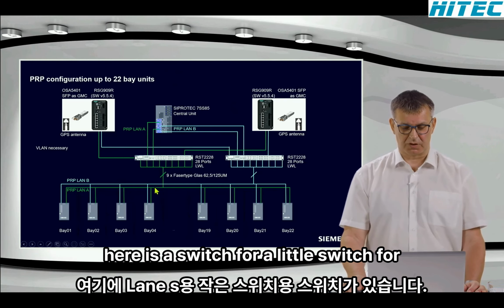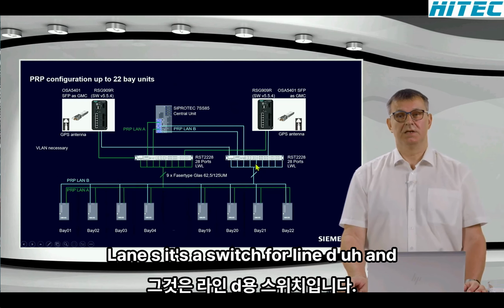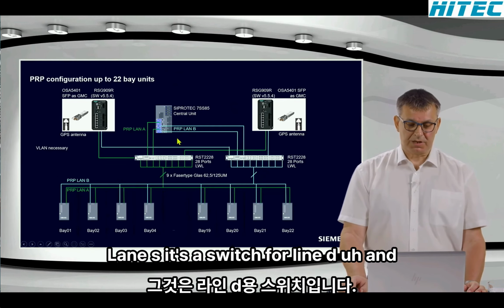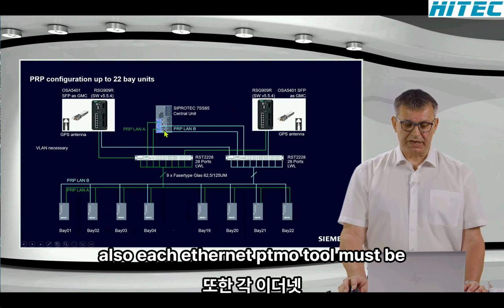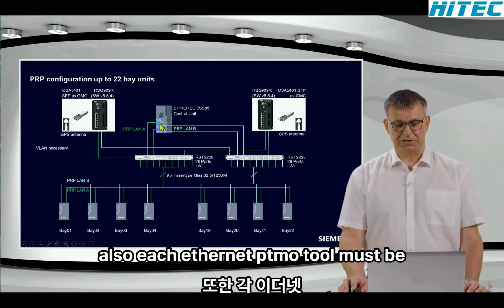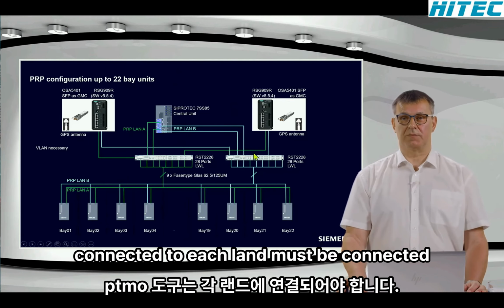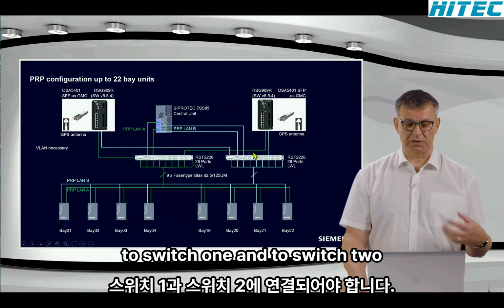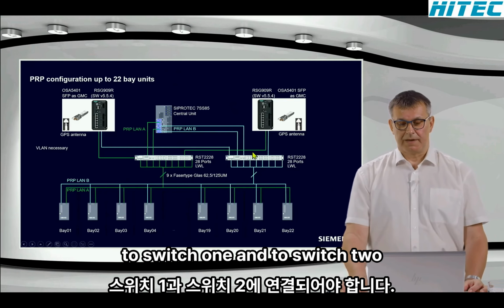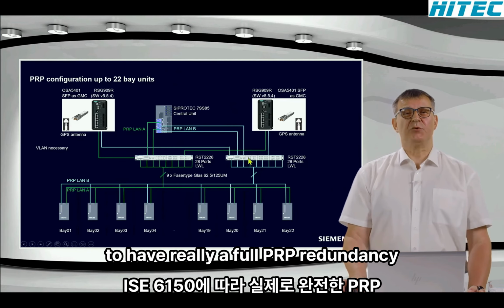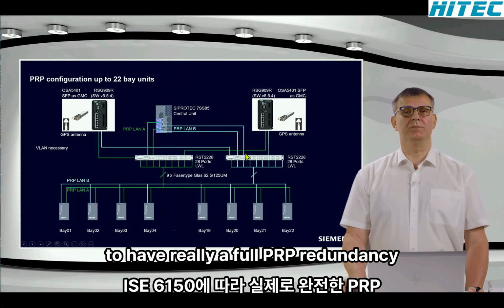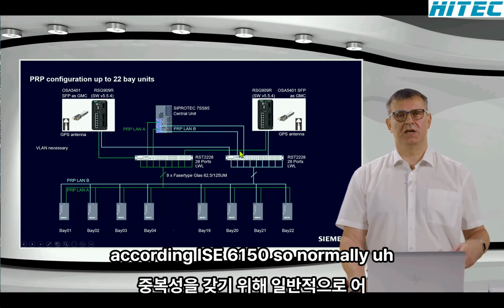Here is the switch for LAN A, that's the switch for LAN B, and each Ethernet BT module must be connected to each LAN, must be connected to switch 1 and to switch 2, to have really a full PRP redundancy according to IEC 61850.